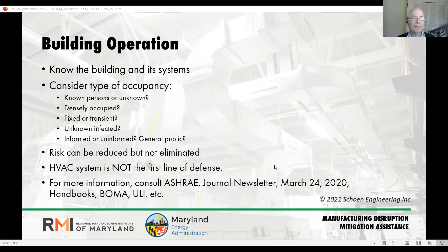These are the strategies, and we're repeating outdoor air ventilation. There are energy-saving controls that under normal circumstances you do want to use, but perhaps not in the midst of a pandemic. So if you have something limiting ventilation based on CO2, as some modern energy-saving systems do, this may be a time to disable that temporarily, and bring it back into operation once the risk has gone down.